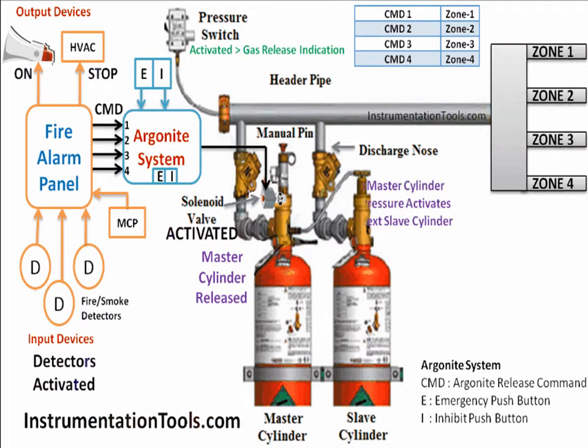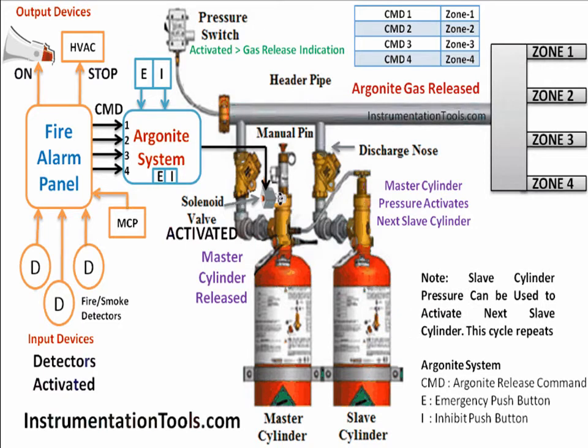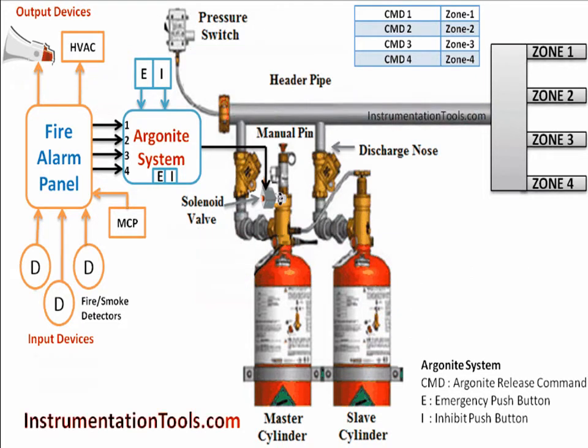In this animation we consider four zones. Zone means areas, locations, or rooms. If fire and smoke detectors are activated in zone 4, then the fire panel sends command 4. The fire alarm panel can send commands from CMD1 to CMD4 depending on the fire and smoke detector activation in the respective zone. The Argonite System then receives the Argonite Release Command from the fire alarm panel.